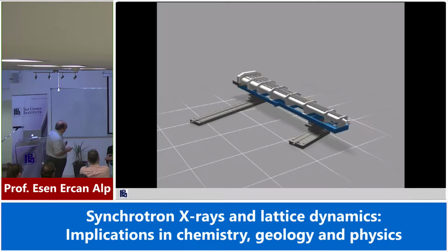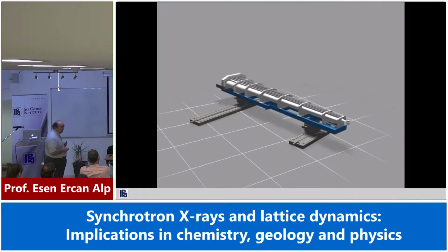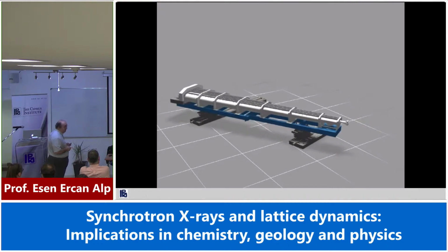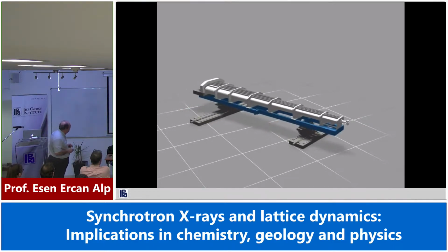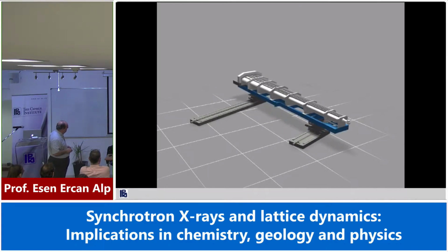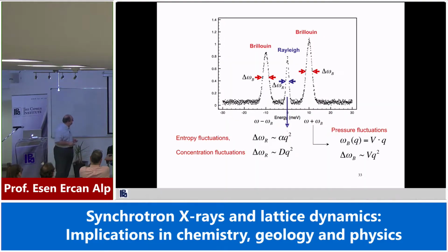And then if you want to go and make some sweeps in the first, second, third Brillouin zone, this is like the world's most expensive Fourier transform machine. Right? So it takes about 2 years to plan, draw, and procure this system. I mean, and then we put about $1.5 million to build this system. It's one of the 3 instruments in the world that has this capability. Right? So we use this to study things like this, for example.